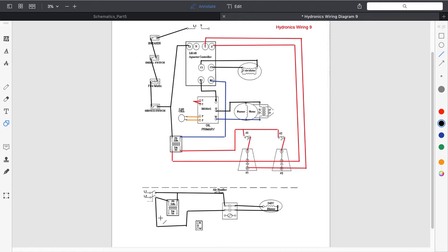Now all we have left here is a 24 volt coil and our contacts for our pipe clamp thermostat. We know that a coil, one side of it always has to go back to transformer common. Let's go ahead and wire that. Come to W, come to R. And again, if you were doing this on paper, we'd want to be a little bit more careful with angles of wire and make sure that you do any jumps for things that cross. When you look at this diagram, the way I have it written, make sure that you know that different wire colors, if they cross each other, do not connect.